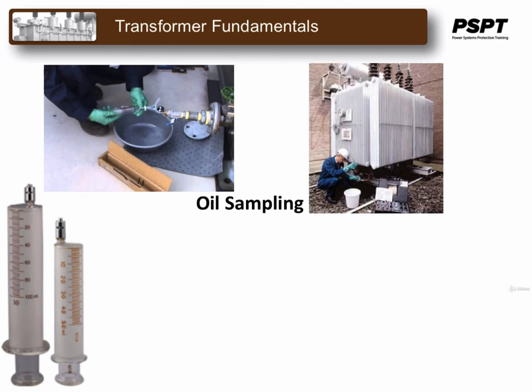Fluids with specific gravity greater than 1 should be sampled from the top because free water will float. For fluids with specific gravity less than 1, such as mineral-based transformer oil, synthetic fluids, or silicon oils, the sample should be taken at the bottom, since water will tend to drop to the bottom of these fluids.